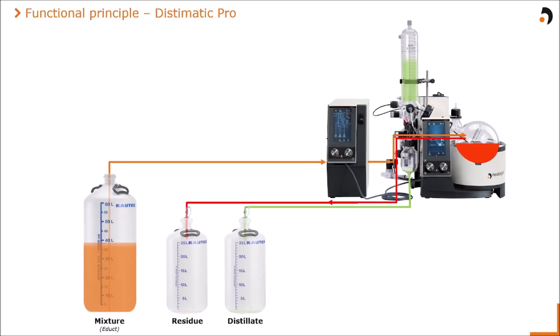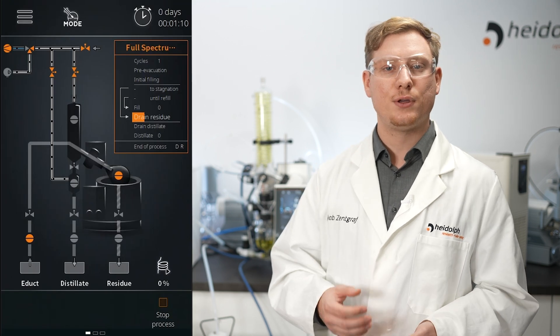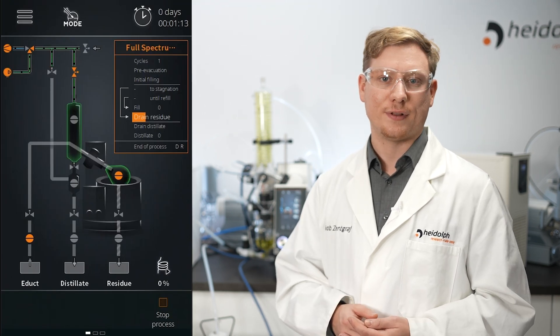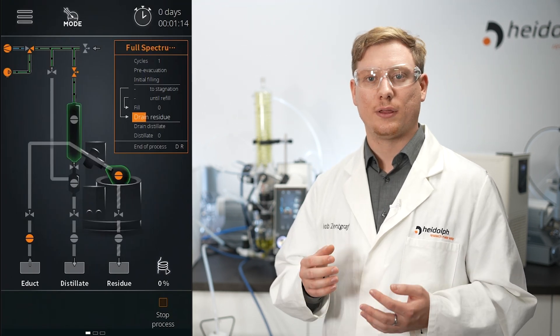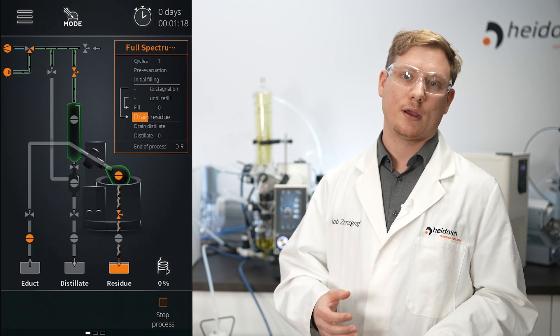For most applications the amount of solvent is significantly higher than the amount of residue, which is why this step will be repeated several times. During this period the concentration of our residue constantly increases inside the evaporation flask. After a while the sensor detects a constant filling level, indicating a mainly pure residue inside the evaporation flask.